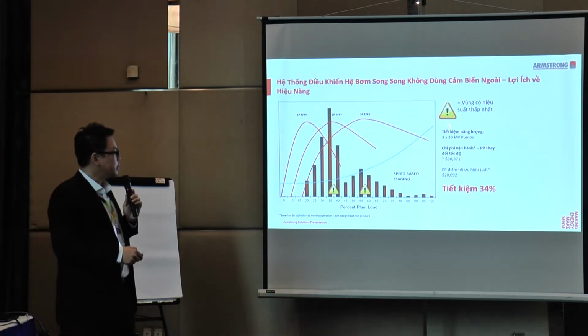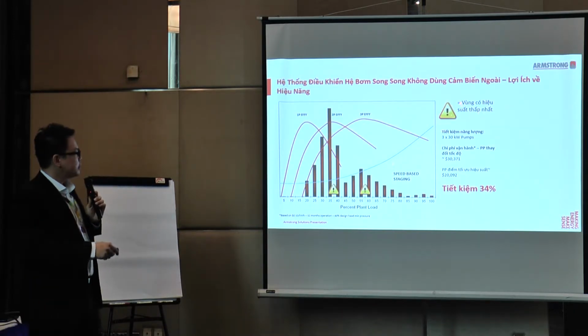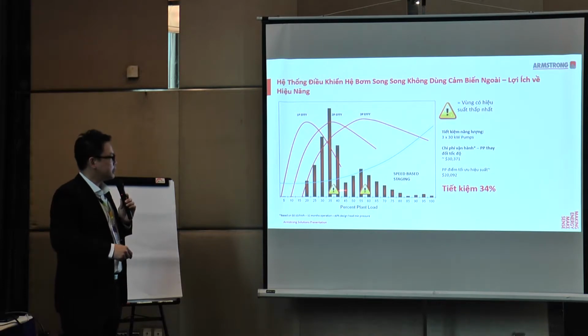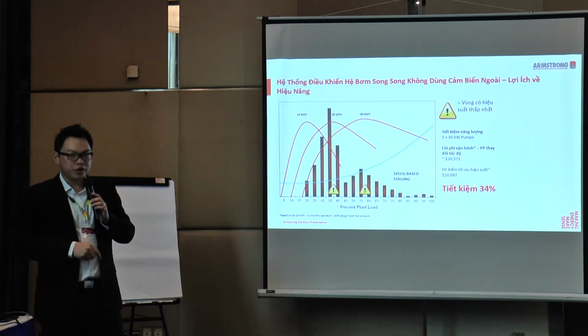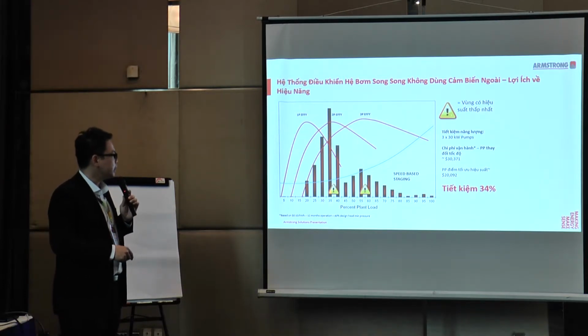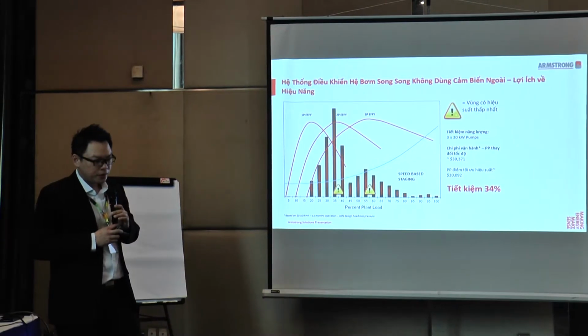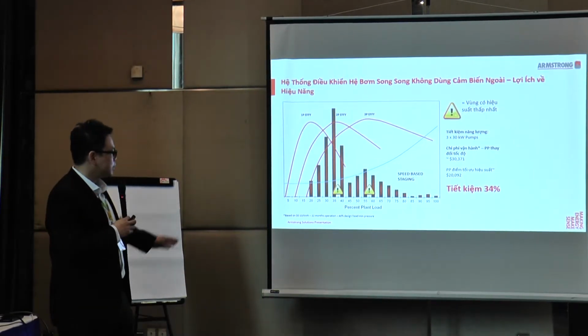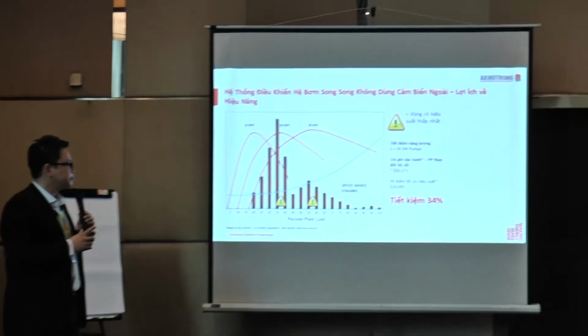Earlier on I talked about these warning signs. I have put the building load profile onto this same graph, and you can see that between 30 to 40%, this is where the system is most operated, and even at 50 to 60%.